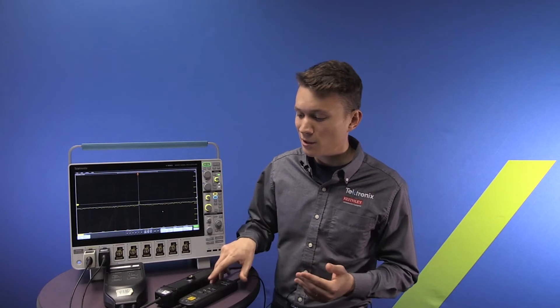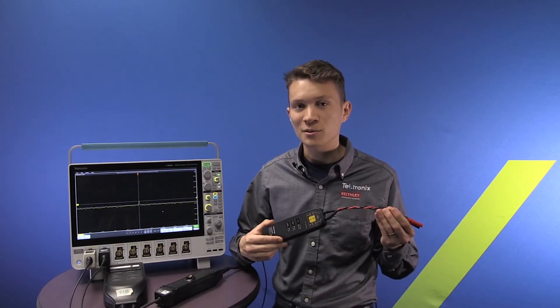When you need to make a voltage measurement with a non-ground reference, use a differential probe like this one.